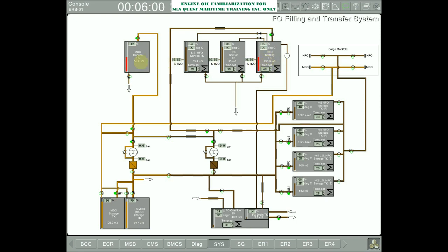So we have to fill up these two tanks using MDO transfer pump and HFO transfer pump. So we'll take suction from number 2 fuel oil storage tank port. So open the two valves there. Open the suction of HFO transfer pump and then trace the line, make sure that fuel oil settling tank filling valve is also open. Yes, it's open. Then trace the MDO transfer pump, suction valve to be open, and MDO service tank is already open.